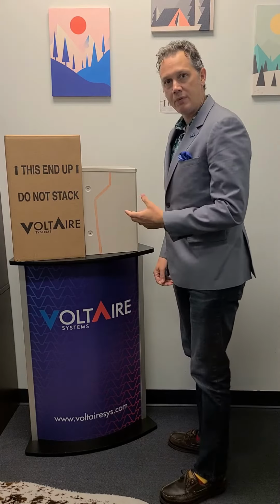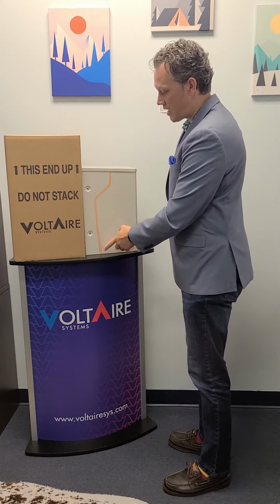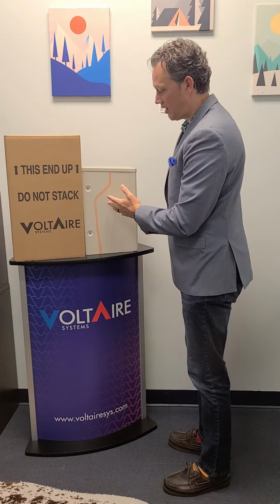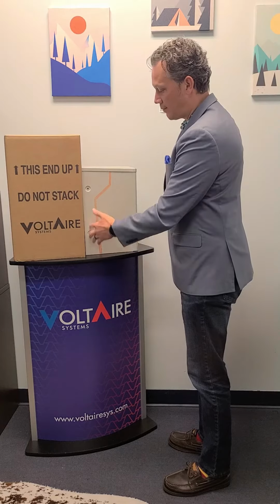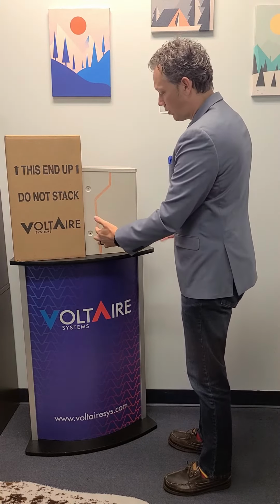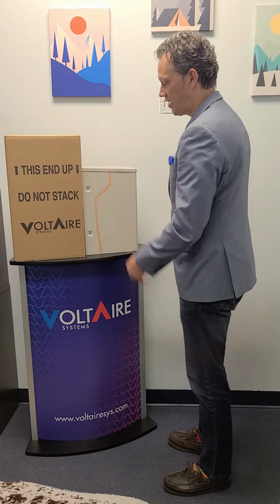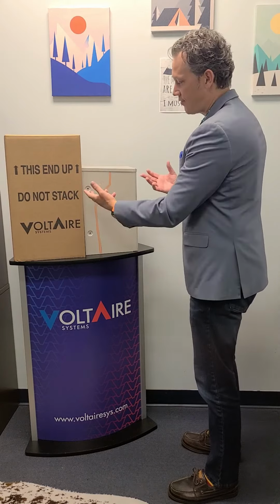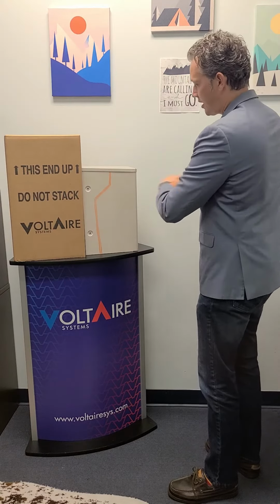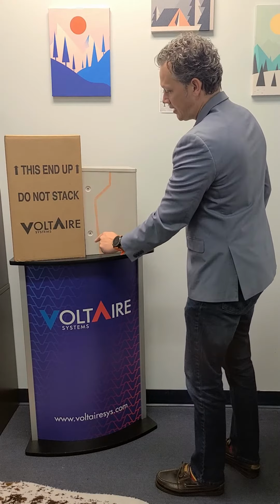To use my prop, it's very important to understand what this line represents. This is the air divider plate. The air divider plate separates the evaporator side and the condensing side. On both sides, you'll have a coil. You'll have your evaporator coil, you'll have your condensation coil, you'll have two fans. So very simply, the paths never meet. Basically, you're creating two C's of air path, ambient air and then enclosure air, and they never mix.